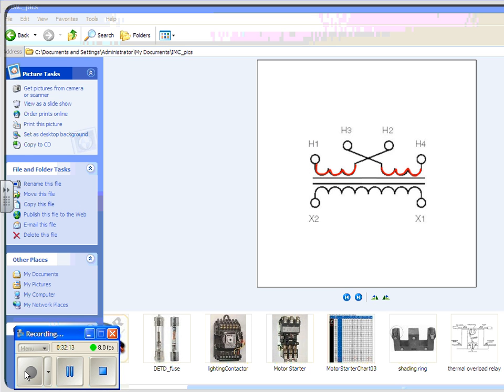And so if we have a higher voltage, how would we hook up the 2 windings so that we have the same voltage drop across both sides? No, in series. We're going to connect them in series so that we have, what are we going to drop across this winding? If we tie H2 and 3 together and put 480 across H1 and H4, we'll put 240 across each one of these 2 windings right here, right? Series circuits are voltage dividers, right? So we want to have this 480 connected in series, so we put 240 across each winding on the top side, and it's a 2-to-1 step down, so we're going to get 120 out of the bottom, right?